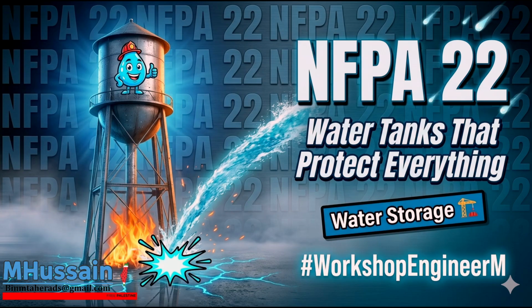Okay, let's shift away from the water inside the tank and look at the structure holding it up. Section 4 focuses on protecting the protector: fireproofing and structural integrity. Section 4.3 outlines the location of tanks. It clearly states that if a tank is located close to a building or a fire hazard, the supporting steelwork must be protected from fire exposure. Now, this concept frequently catches junior engineers off guard. The immediate instinct is to ask, why do I need to fireproof a water tank? It's a massive heat sink filled with hundreds of thousands of gallons of cold water.